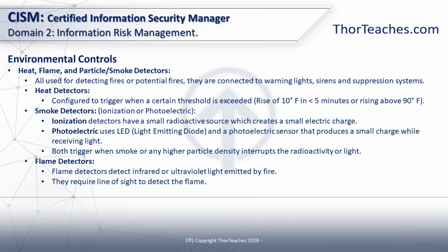Most of the systems are on a delay, so the alarm and the warning lights go off. Then there's a 20 or 30 second delay where staff can check whether there is an actual fire, and if there is, they can exit the area. And after the delay, the fire suppression system will kick in. The if-then on the heat sensor could also be: if the temperature is above 90 degrees Fahrenheit or 32 Celsius, then sound the alarm and start the timer.